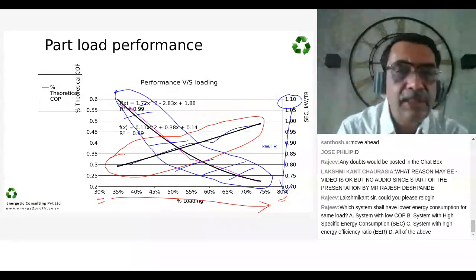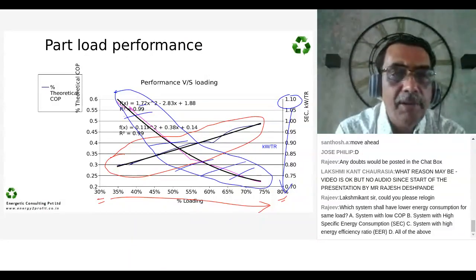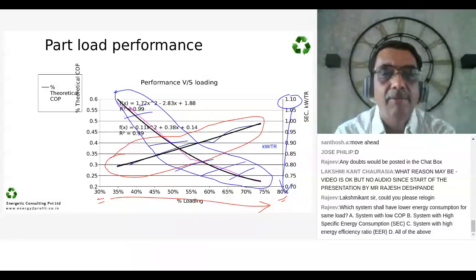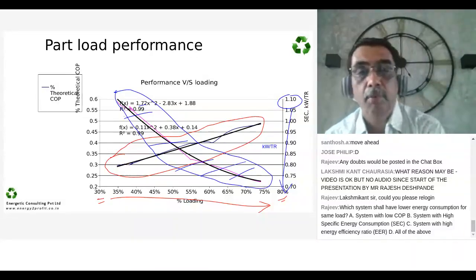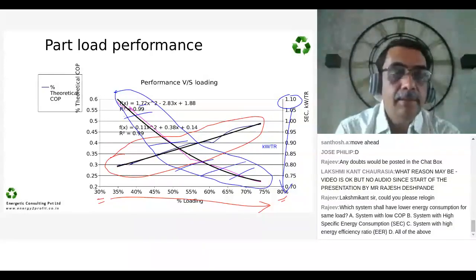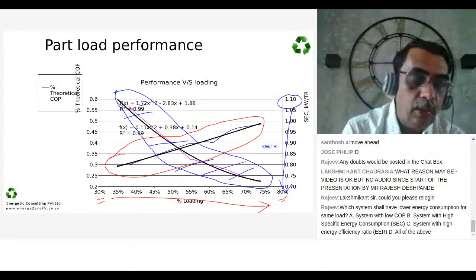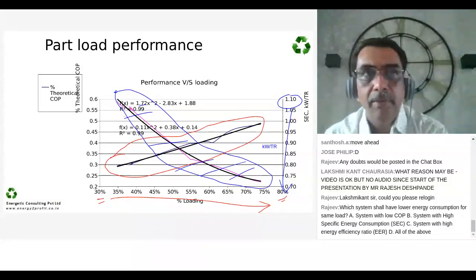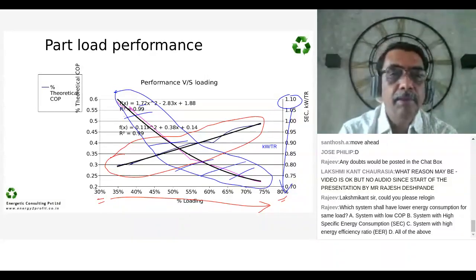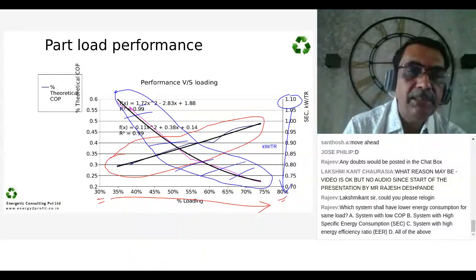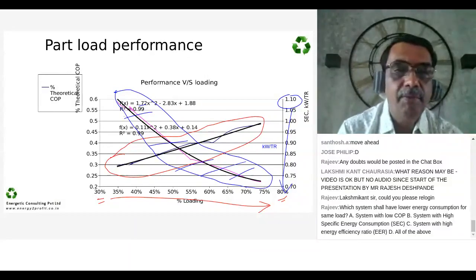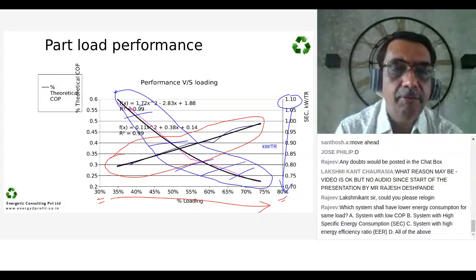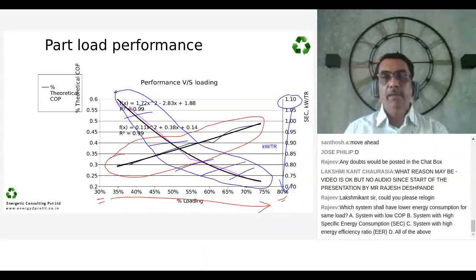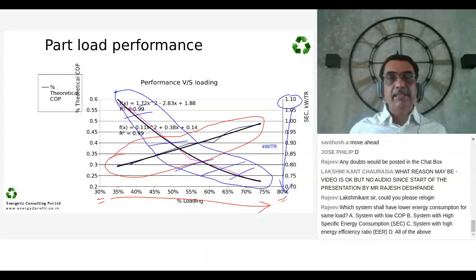So the poll is posted. All of you can. I am reading it for everybody's benefit. Which system shall have lower energy consumption for same load? Lower energy consumption, lower kilowatt consumption for same load, same TR output. System which has got lower COP, system which has got higher specific energy consumption, system which has got high energy efficiency ratio, or all of the above. Please record your answers in the polling option.